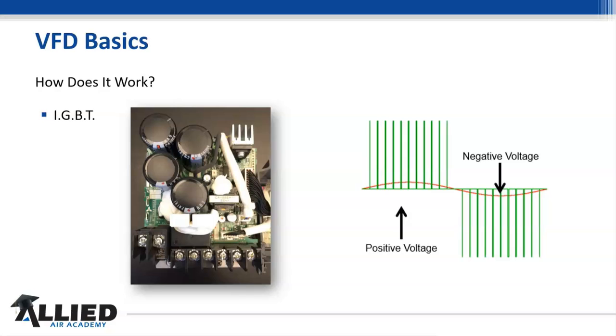Because this is the wave that we're talking about. Now, after the DC voltage is cleaned up, it arrives at the DC bus on the inverter section, and it's passed through a series of diodes called IGBTs, which stands for insulated gate bipolar transistors. Okay, so it's going to have to pass through that, and they act as triggers and send out the DC voltage in short bursts, positive and negative. That's why you get these waves, and it actually looks like an AC volt sine wave.